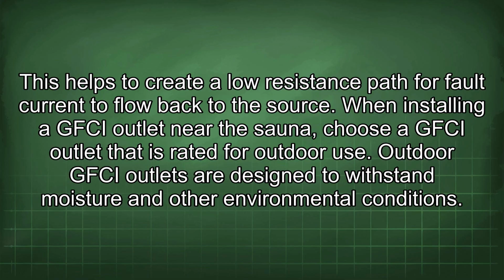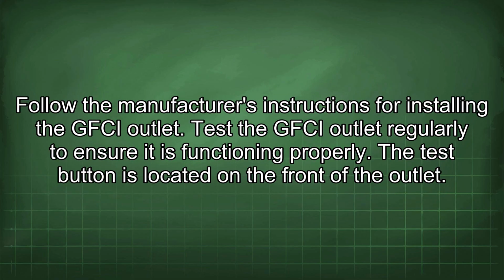When installing a GFCI outlet near the sauna, choose a GFCI outlet that is rated for outdoor use. Outdoor GFCI outlets are designed to withstand moisture and other environmental conditions. Follow the manufacturer's instructions for installing the GFCI outlet. Test the GFCI outlet regularly to ensure it is functioning properly.